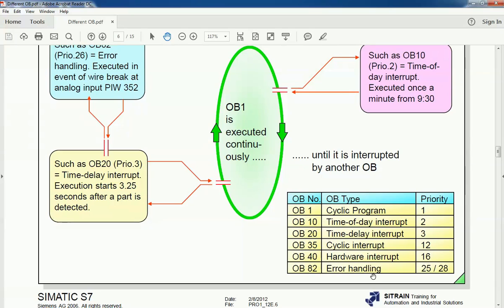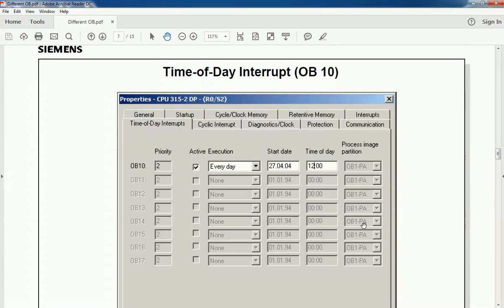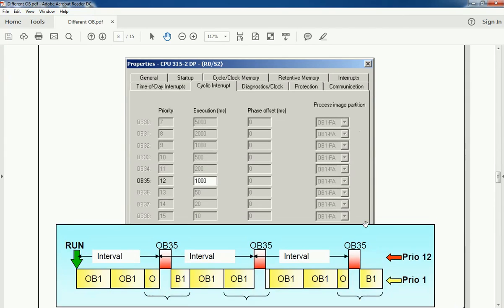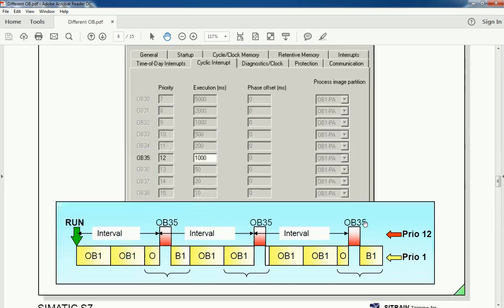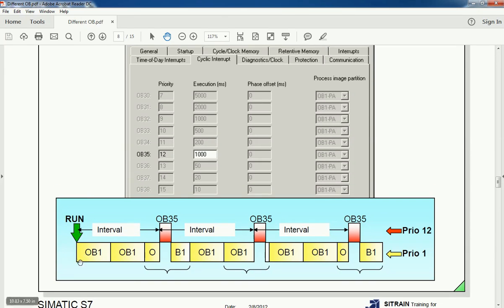You can configure the time-of-day interrupt OB10 in the PLC hardware properties. In the execution cycle diagram, OB1 is continuously executing as per its interval. Meanwhile, OB35 — the cyclic interrupt OB — will execute when its interval completes. OB35 has higher priority: priority 12 for OB35 and priority 1 for main OB1.